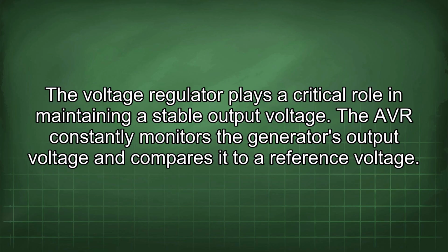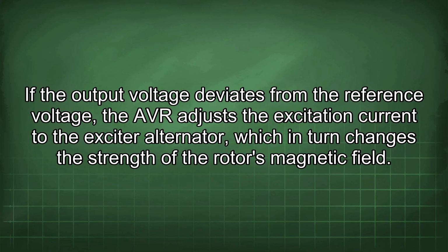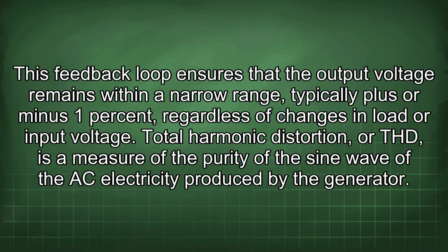The AVR constantly monitors the generator's output voltage and compares it to a reference voltage. If the output voltage deviates from the reference voltage, the AVR adjusts the excitation current to the exciter alternator, which in turn changes the strength of the rotor's magnetic field. This feedback loop ensures that the output voltage remains within a narrow range, typically plus or minus 1%, regardless of changes in load or input voltage.